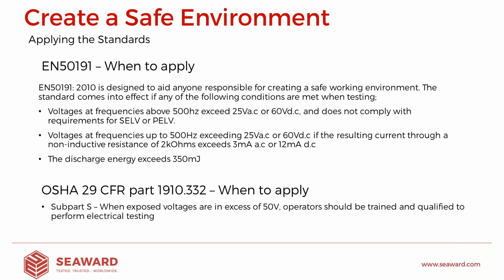Now, OSHA 29 CFR Part 1910.332 talks about, again, the limits for safe working. And in this case, it's where exposed voltages are in excess of 50 volts. So again, we definitely know that for most hypot tests, we're going to be well in excess of 50 volts. And Subpart S in particular talks about the training required in order to make your operators qualified to perform such testing. So there is plenty of guidance out there. We will link to the relevant websites a little bit later on in the presentation.